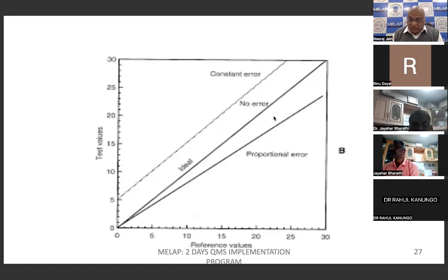Your control results are okay, QC performance is okay, everything is okay. So why new machine is behaving in a different way? Because you cannot say, if a patient is coming, you are receiving a sample for TLC in the morning, and suppose it is 22,800. In the evening, it is coming 16,400, just because of instrument variation. That is not acceptable. We have to check all these things.